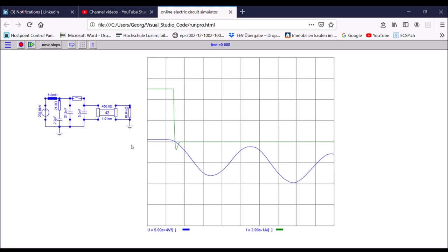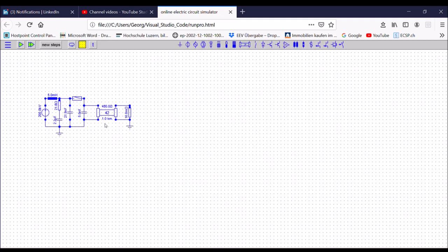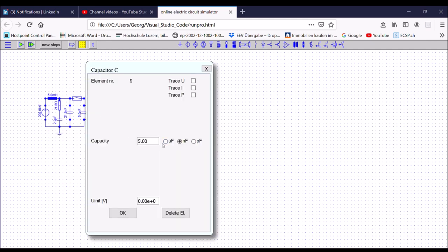There is always a race between clearing the current and the cooling of the arc, because the arc is still ignited here. So the breaker tries to cool the arc so much that the recovery voltage cannot heat it up successfully anymore, so the current can be interrupted. I will now show another case where the breaker will fail. So I use the same model as before. The only thing I do, I change the value of this stray capacitor here at the breaker.